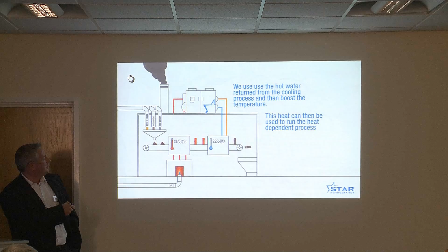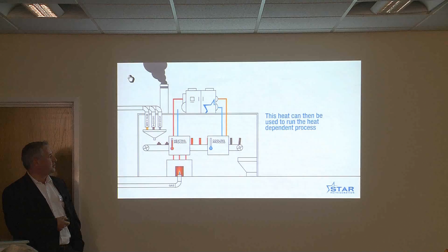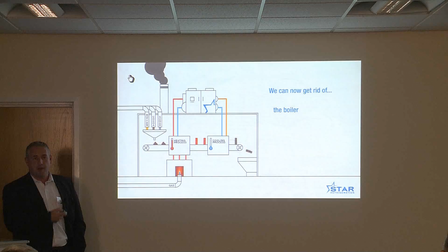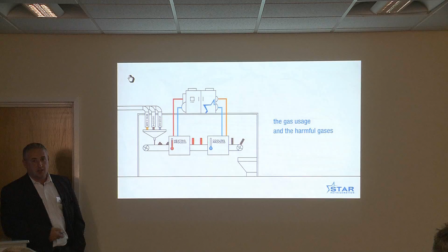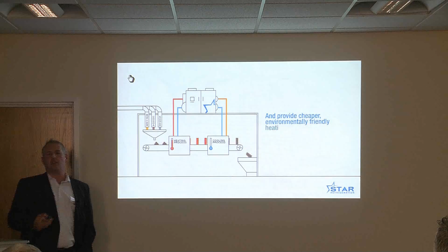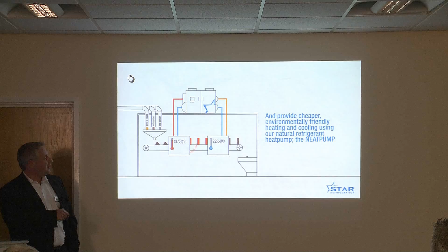What we said was, if we capture the waste heat and deliver it back into the heating process - of course there's no perfect situation, a lot of processes must use steam at 130. But when you start measuring what quantity of heat, what time of day, you start realizing steam has been overused over the years in the sense that it's quite convenient. If you have to transport kilowatts of heat across a reasonable distance, steam is quite good. But the reality is we quite often use steam at fairly low temperatures.